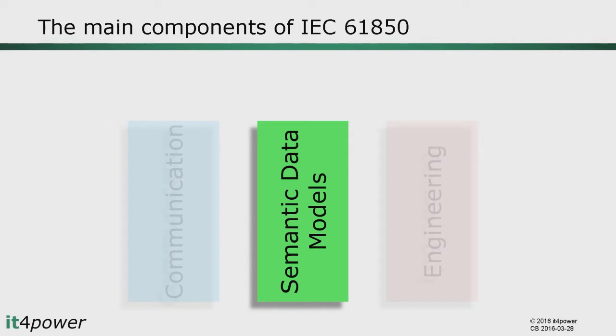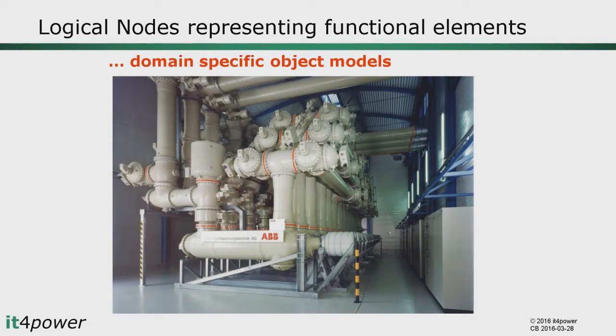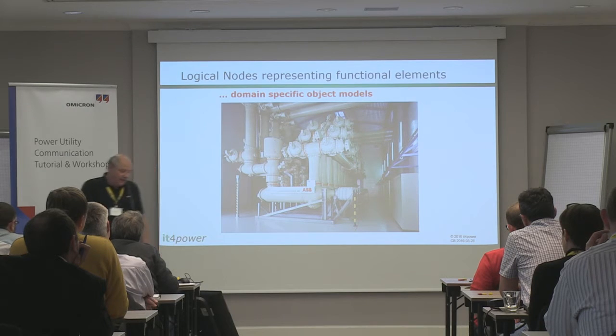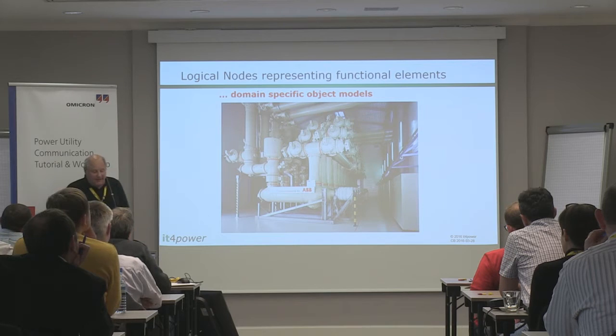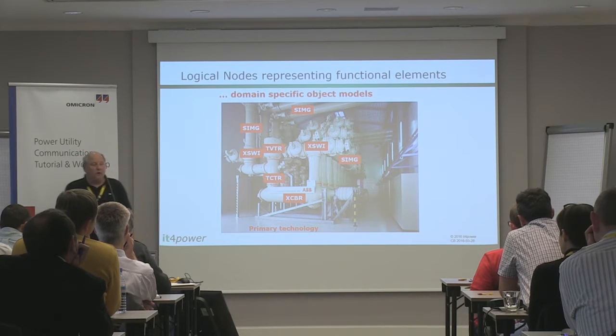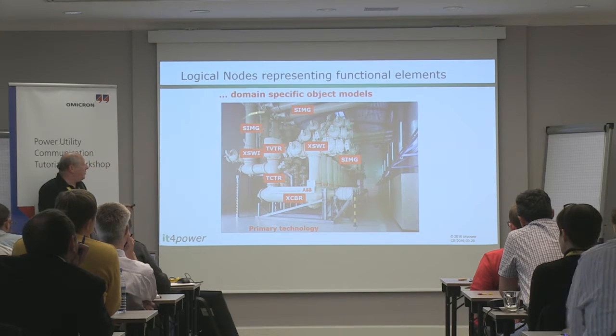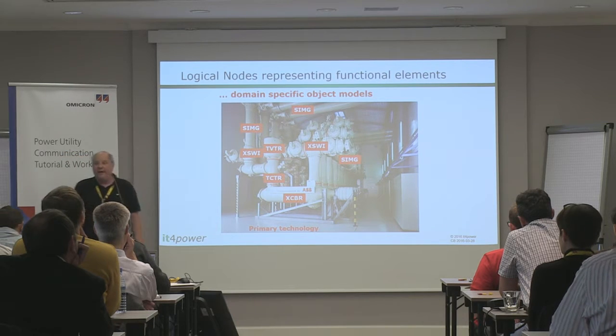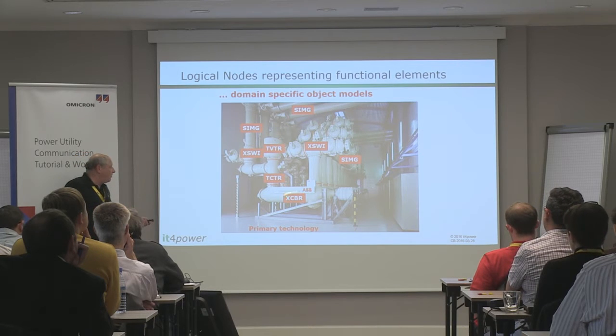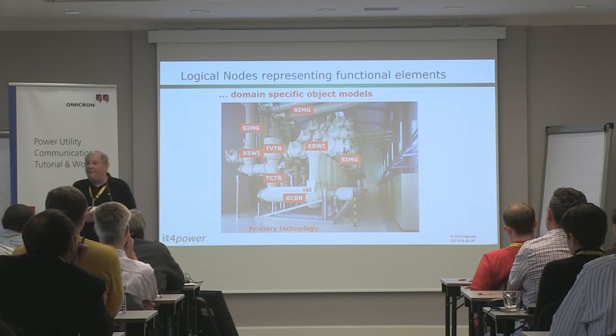Now let's look beyond communication at the data models. The main concept in 61850 is the logical node — a grouping of information representing functional elements. For example, in a switchgear context, 61850 defines logical nodes such as XCBR for a circuit breaker, XSWI for other switches like disconnectors or earthing switches, voltage and current transformers, and even gas density measurement units for gas-insulated switchgear. Everything you can get as information from a circuit breaker is grouped together in the XCBR logical node.